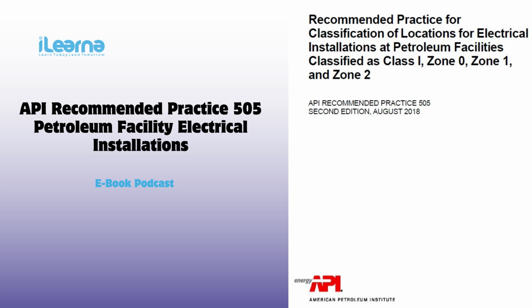They definitely did. But before we get too far into how API 505 classifies all these different areas, I think it's important to understand some of the key concepts that it's based on. Definitely. Right? So, what are some of those terms that are really important to understand? Well, first off, they make a clear distinction between a flammable liquid and a combustible liquid. Okay, so what's the difference there? It all comes down to that flash point we talked about earlier. Remember, that's the lowest temperature at which a liquid can give off enough vapor to ignite.